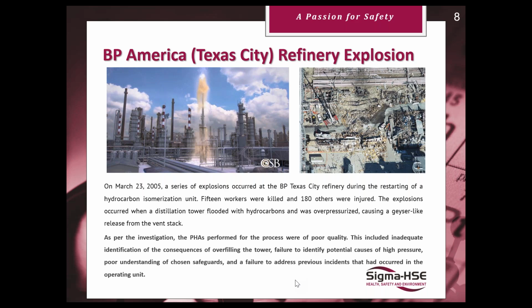What happened was there was a failure of a level instrument within a distillation tower. They didn't receive notification that they had overfilled it, and this resulted in flooding of the tower, forcing hydrocarbons out of a vent stack, as shown in the Chemical Safety Board picture, and shooting fireballs into the area. This resulted in demolition of those trailers, damage to the unit, and unfortunately 15 deaths and 180 injuries.